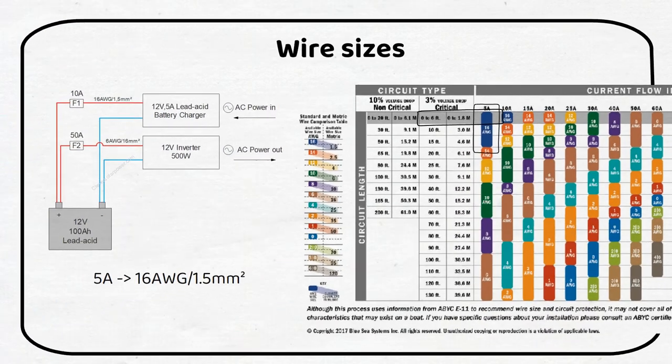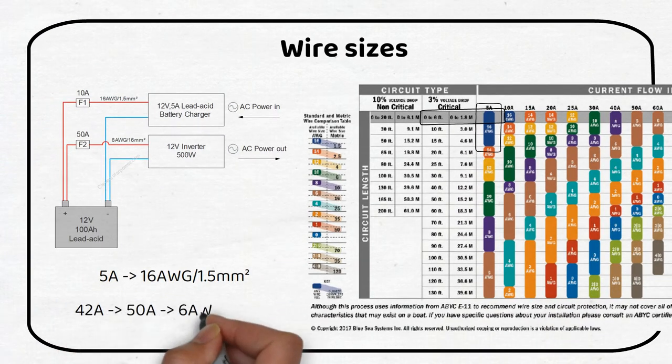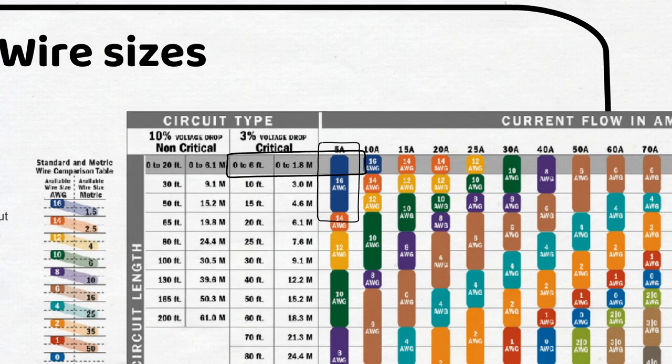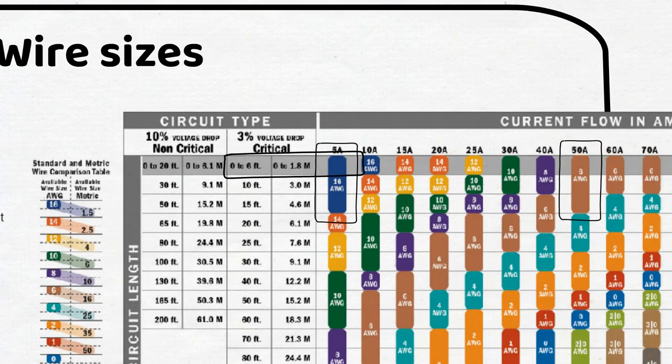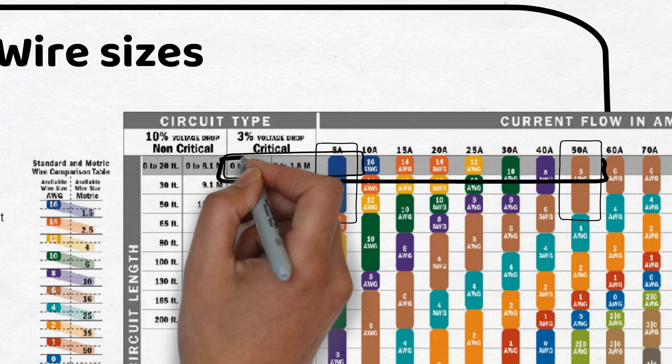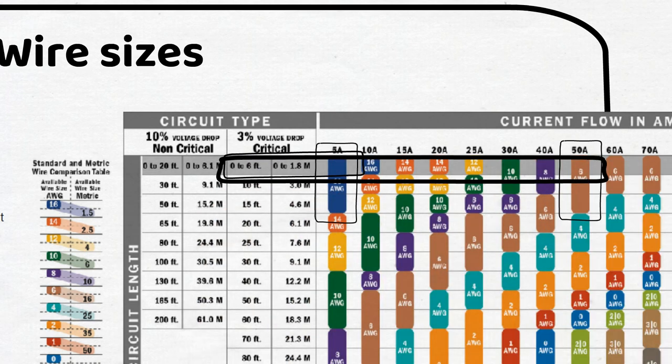The current from the inverter is 42 amps. The closest we can see in the table is 50 amps. If we keep the length of the wire under 6 feet we can see that we can use a 6 gauge or 16 millimeter square wire.